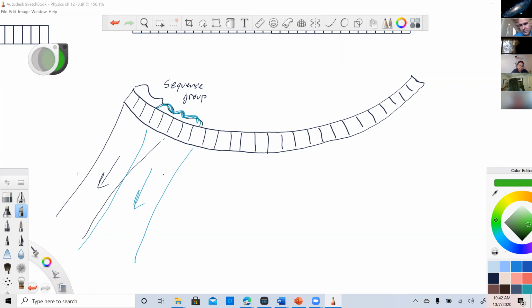And this gap right here between the two is going to cause more problems the further away from the transducer we get. So just like with the vector shape of the mechanical or the linear phased array, the farther away you get, the bigger the space is in between beams. So there's a little bit of a loss of information the farther away you get.